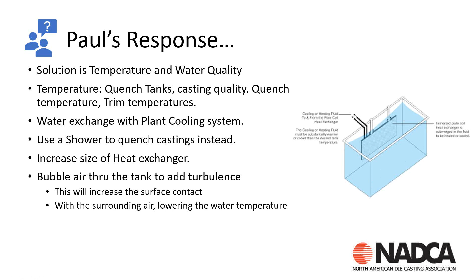Another thing that we did was we ended up bubbling air through the tank to add turbulence. So we put a water line down on the bottom. It was basically a pipe with holes in it like a manifold hooked up to an air line. So we would have a constant stream of bubbles coming up through the water. That increases the overall surface contact with the surrounding air, lowering the water temperature. So it's a way to externally remove heat along with the heat exchangers that are tied to the system.